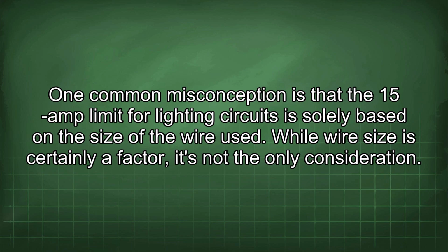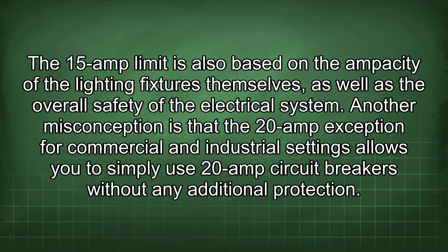One common misconception is that the 15 amp limit for lighting circuits is solely based on the size of the wire used. While wire size is certainly a factor, it's not the only consideration. The 15 amp limit is also based on the ampacity of the lighting fixtures themselves, as well as the overall safety of the electrical system.